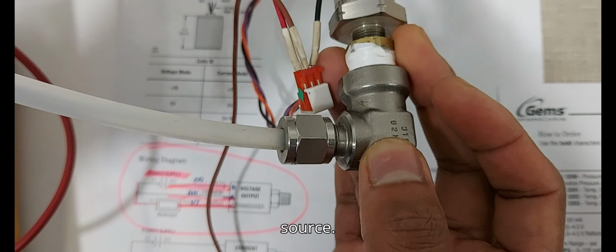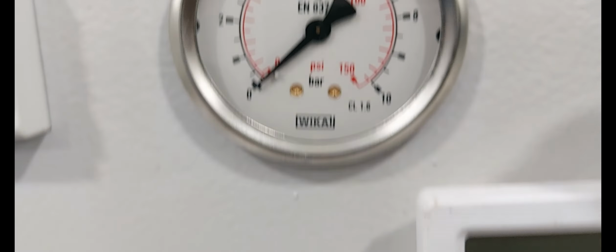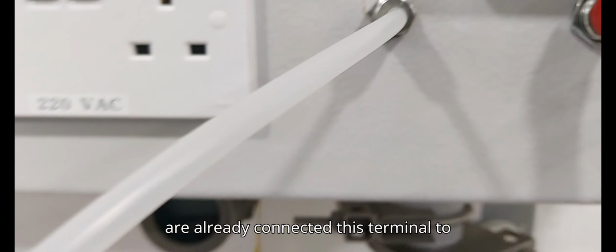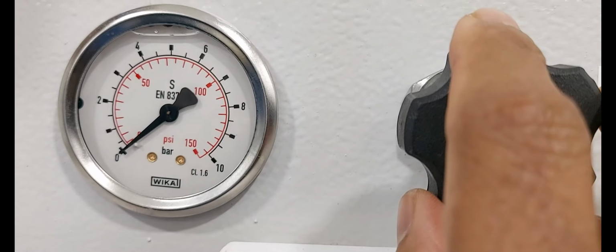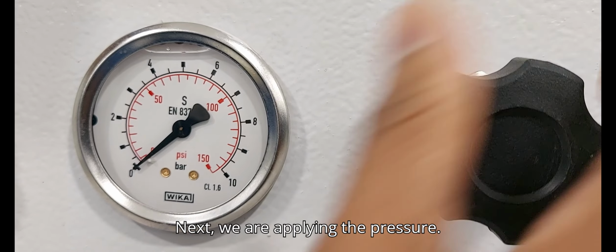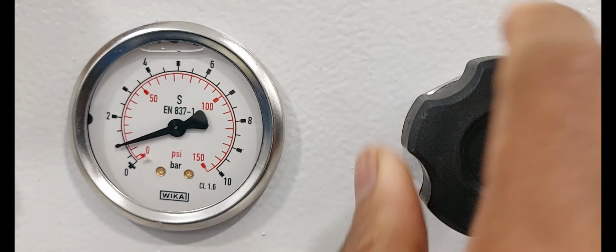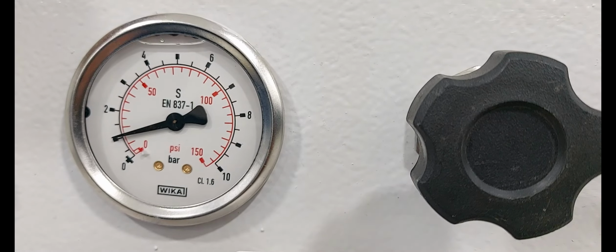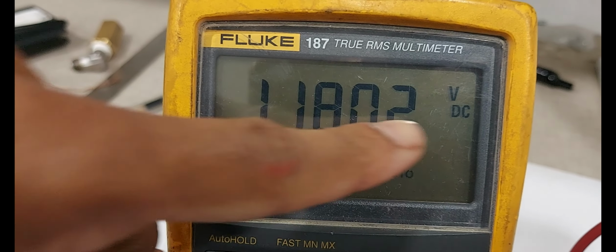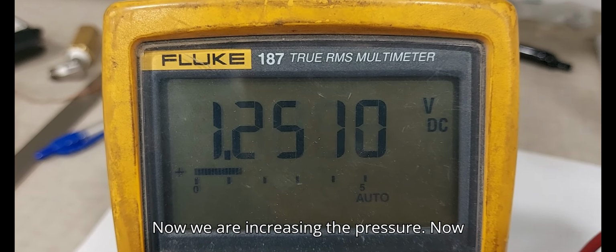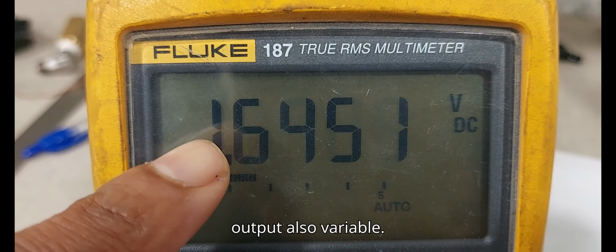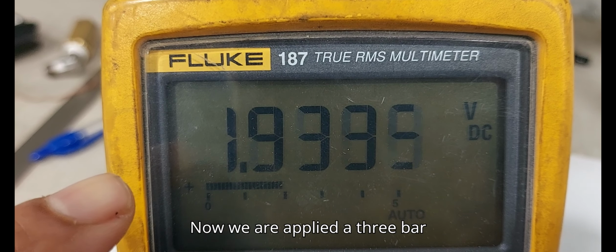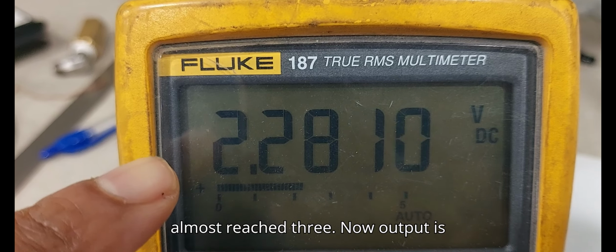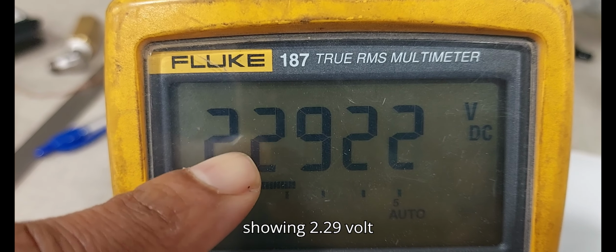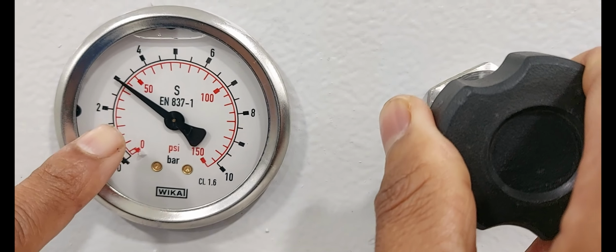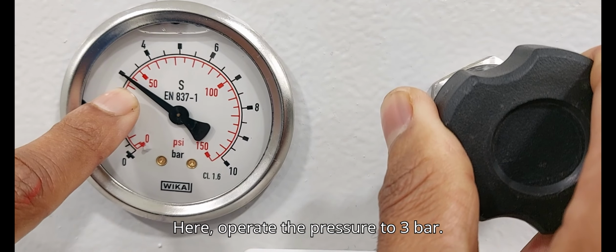Next we are connecting the pressure source. This is inlet gauge. We have already connected this terminal to transducer. Next we are applying the pressure. Okay, now 1 bar almost reached, 1.18 volt DC. Now we are increasing the pressure. Now output also varies. Now we have applied 3 bar. Now almost reached 3. Now output is showing 2.29 volt DC. We applied the pressure to 3 bar.